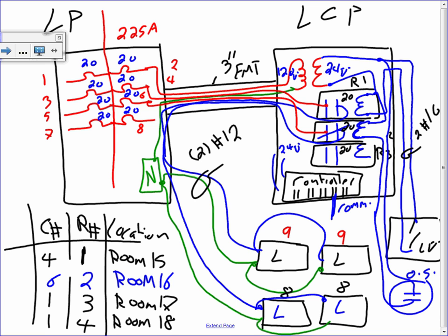Nobody's moving in this room, so the sensor turns the light off. Since nobody's moving, it sends the signal to the HVAC controller. There's a damper in this room, and we're heating it for nothing, so why not shut that damper? This saves energy, so they shut certain dampers off, or lower and control the speed of the VFD on the air handling unit.